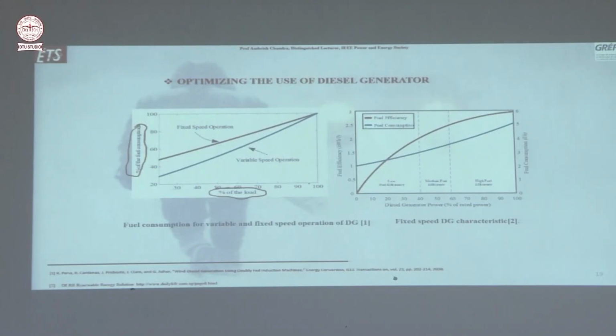Suppose the diesel generator is loaded at 100% capacity, then efficiency is very good. But if you reduce the load, suppose to 30%, you still have 50% of fuel consumption with fixed speed operation. The red line is fixed speed operation, blue line is variable speed operation of diesel engine. With variable speed operation, there is a big advantage, a lot of savings if you are using variable speed diesel generators. So this is what is being done nowadays.